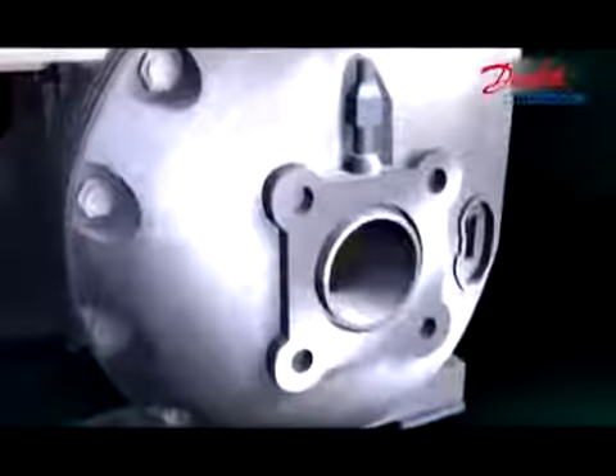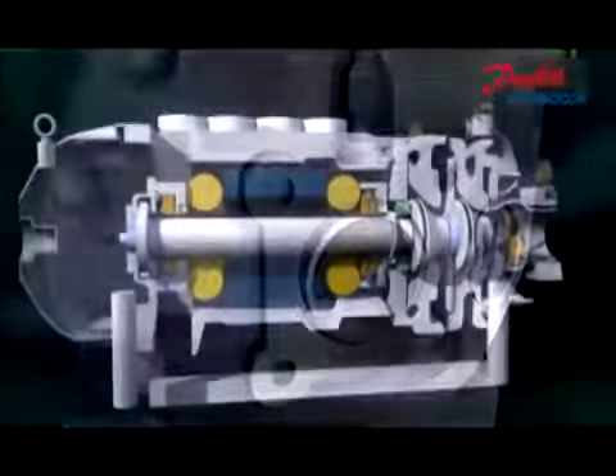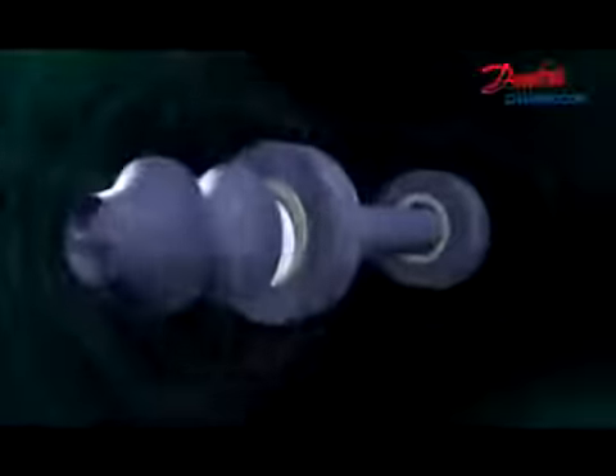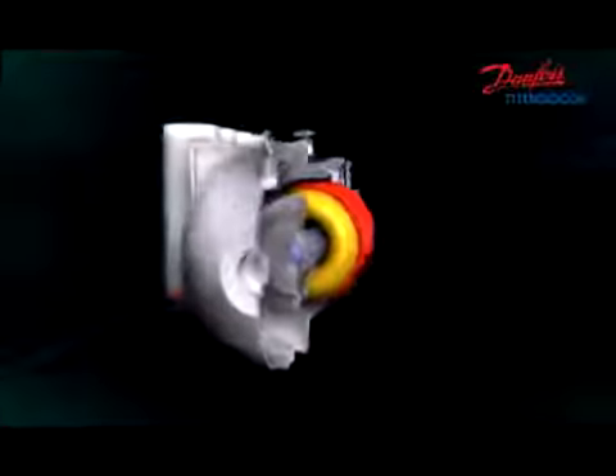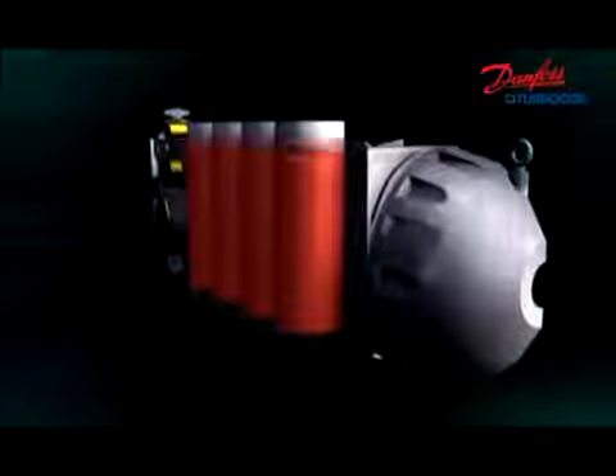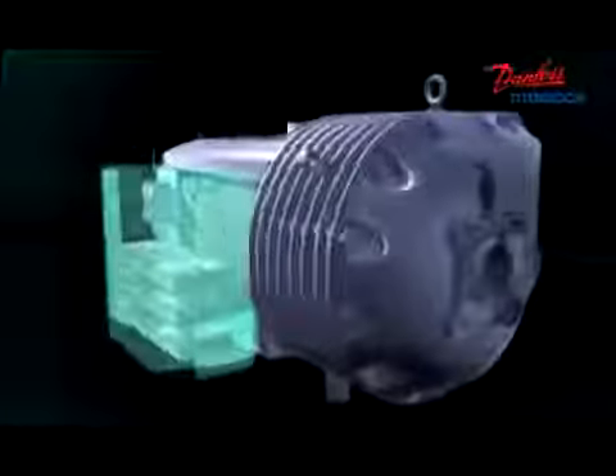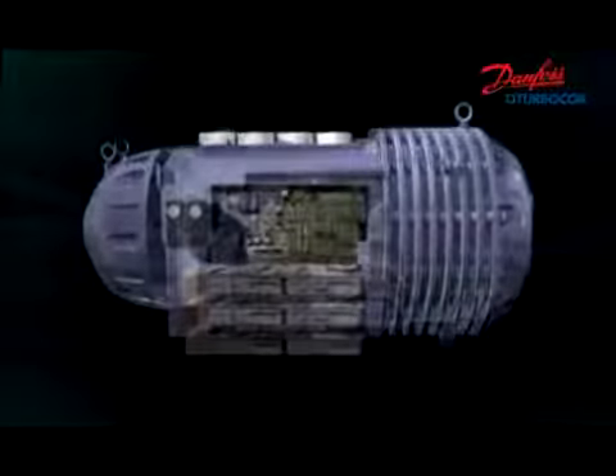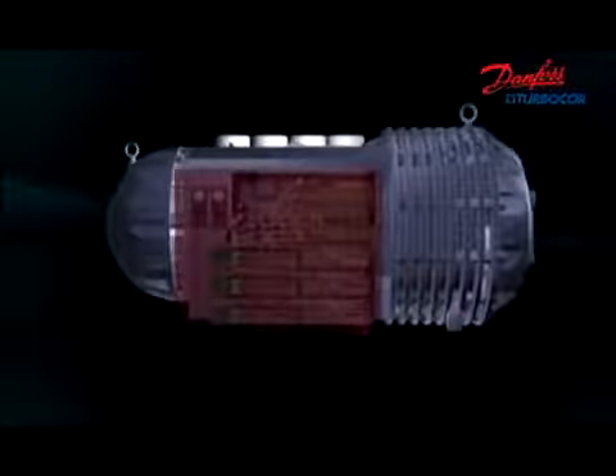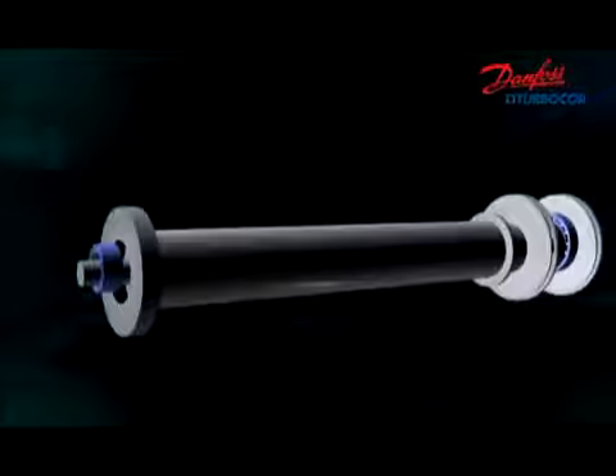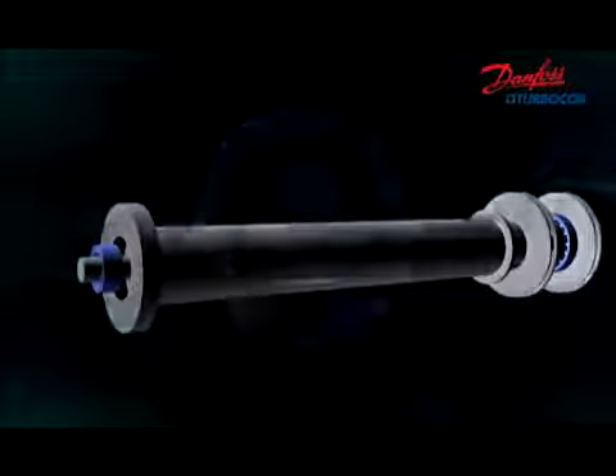All new designs for high reliability are embedded in Danfoss Turbocor. In case small objects are sucked into the compressor, the auto balance feature of the bearing keeps the shaft precisely in the center of the bearings. In case of power outage, the motor turns into a generator and charges the DC bus capacitors so that the motor can come to a controlled stop and de-levitate as normal. In the event of a central controller failure, touchdown bearings are used to prevent contact between the rotor and other surfaces in order to protect the compressor.